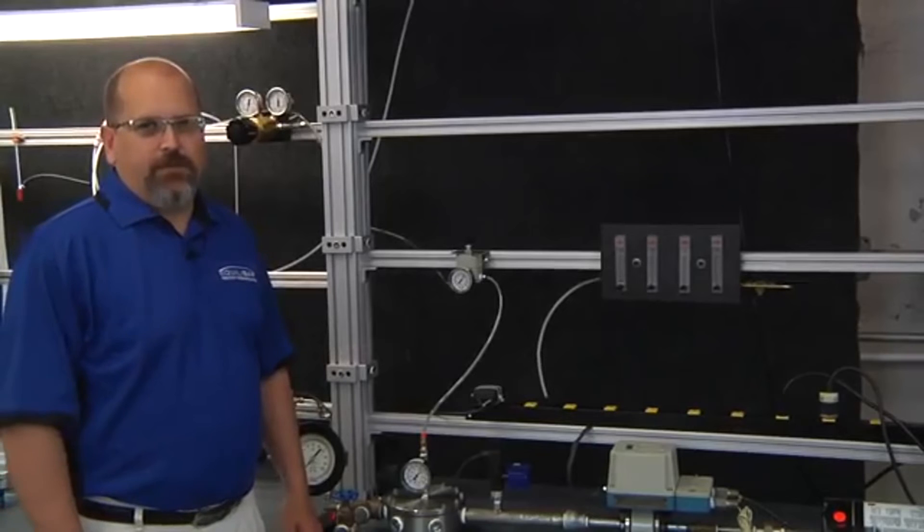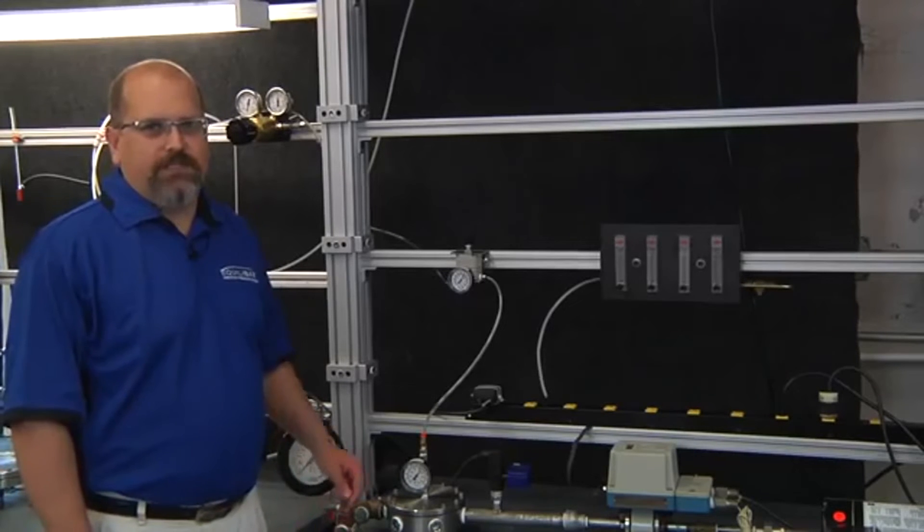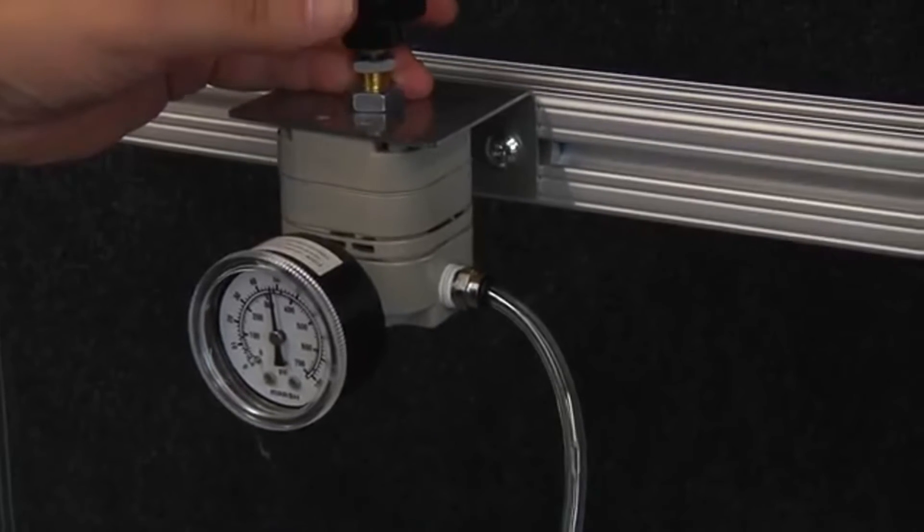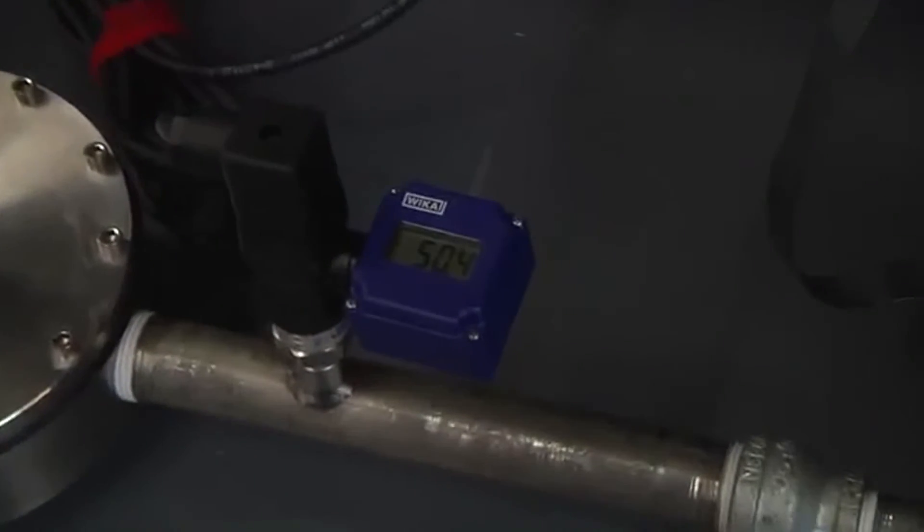What's important is the repeatability of the flow control we can achieve. When I reduce the pressure back to 50 psi, the flow in the system comes right back to 4 gallons per minute through the flow meter.